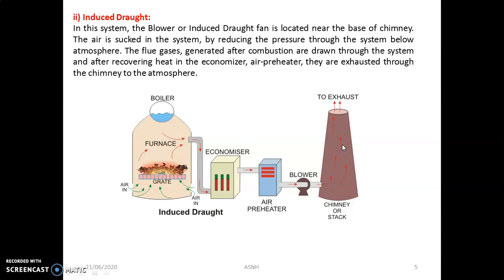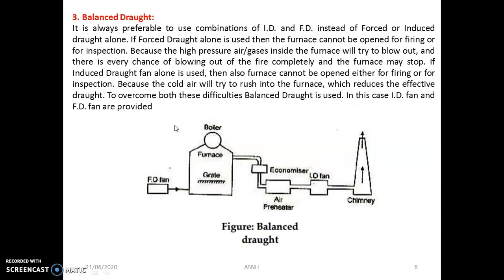The main difference between forced and induced draft is: in forced draft, the blower is placed in the furnace area and continuously blows air, pushing the flue gases in the forward direction. In induced draft, the blower is placed just before the chimney — the flue gases arriving from the air pre-heater level are poor in velocity, and the blower increases their velocity so they exit through the chimney.